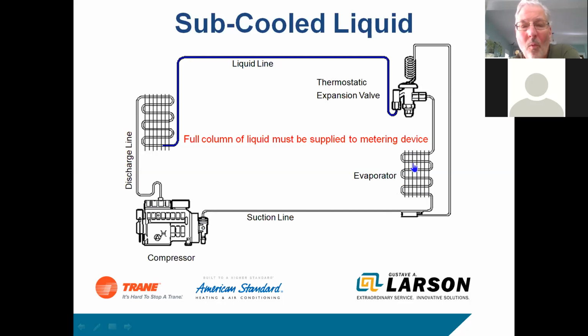Okay, so what happens if I have high superheat here? Say 28, 30, 40, 50 degrees of superheat. Could be almost anything causing that. High superheat here could be we're not feeding liquid to the valve. So the first thing you want to do, of course, is check to make sure it's charged properly. If we are feeding liquid to the valve, we've got our 10 degrees of subcool, and we're still seeing high superheat here, it could be a couple of things. Could be a high load. I've seen cases where the ductwork came apart in the attic and we're drawing 140-degree attic air through there. That'll drive your superheat through the roof.